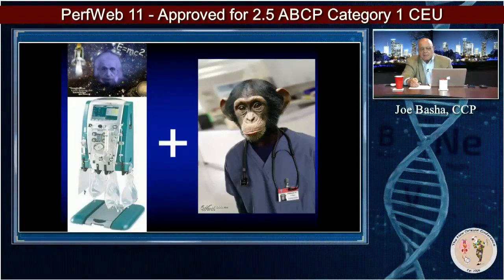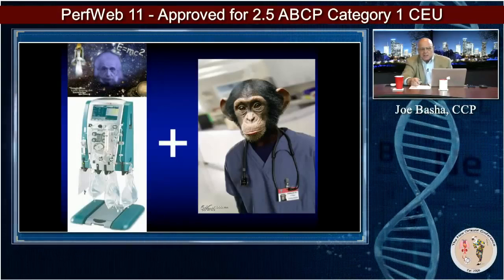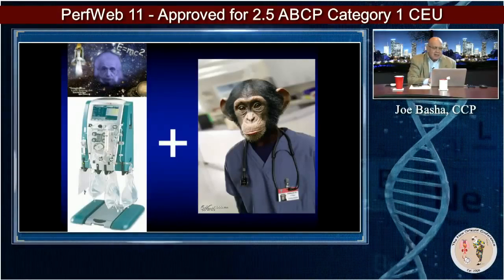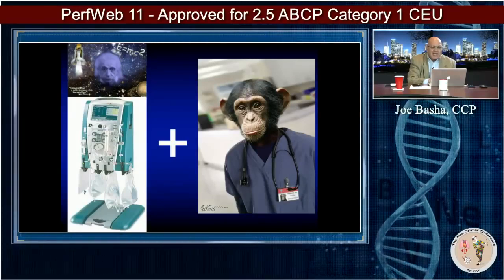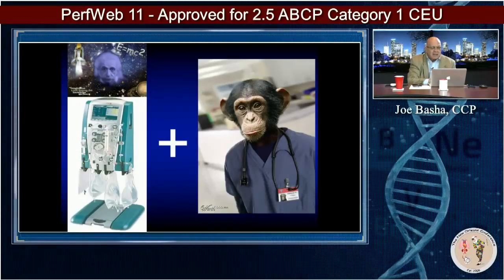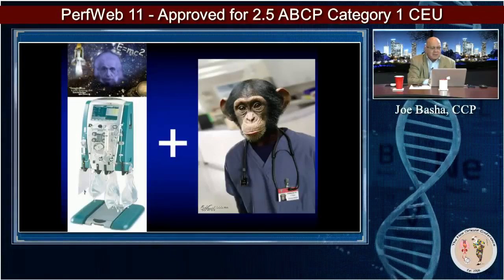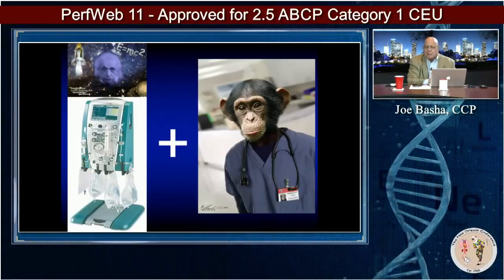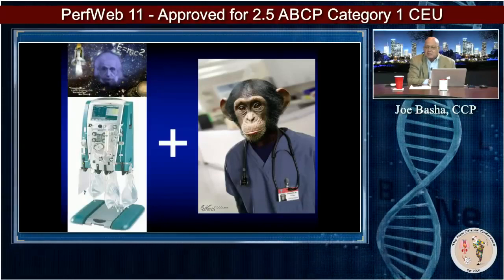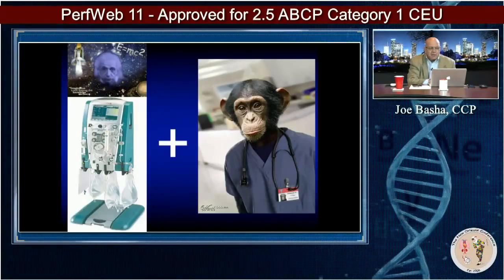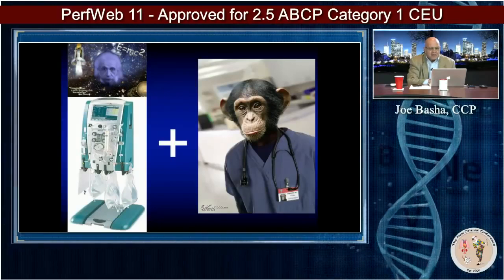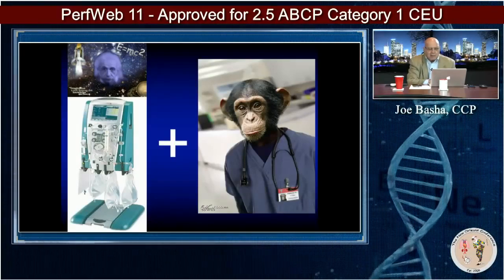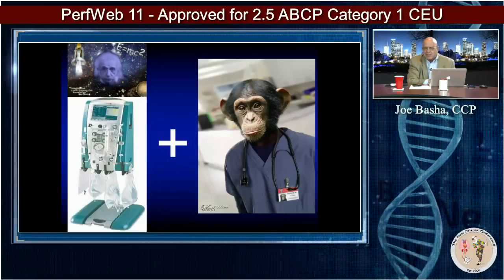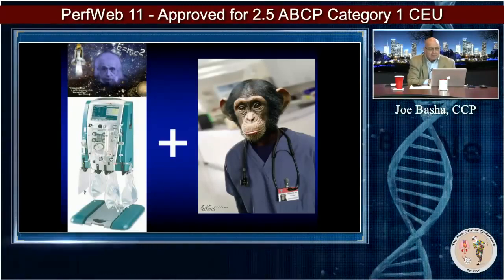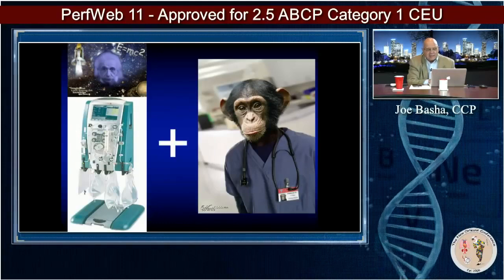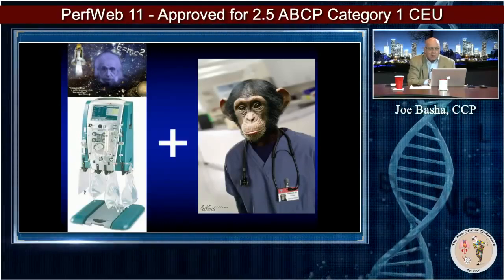It is a gravimetric device, meaning that each of those bags you see down here are on scales. You have replacement fluid bags here, and an effluent or waste bag here. These are 5-liter bags. All of these weights have to be equal, so that if you're adding X amount from one bag and you want zero balance, that amount had better be over in this bag by weight.